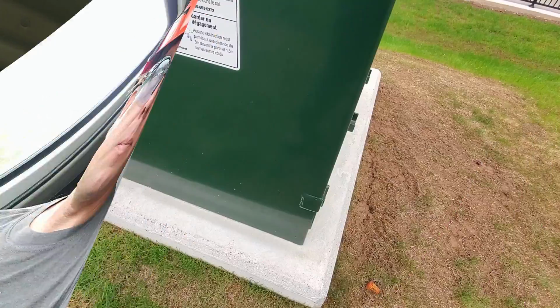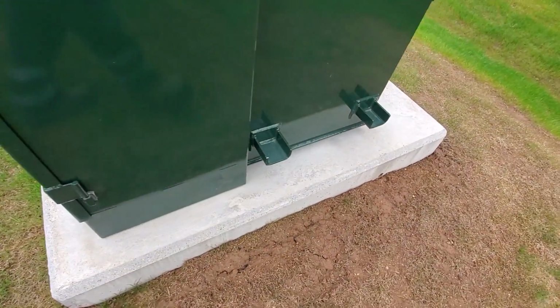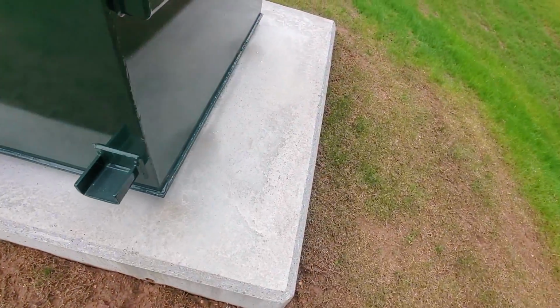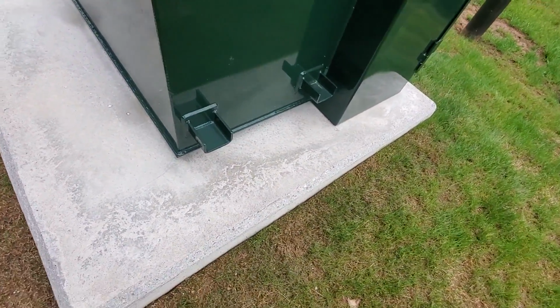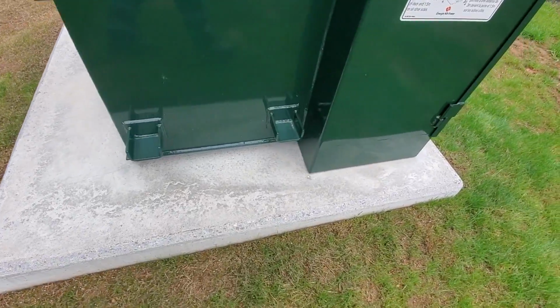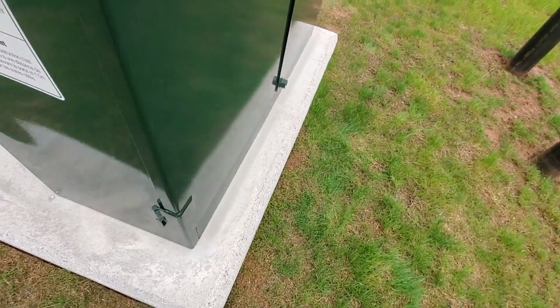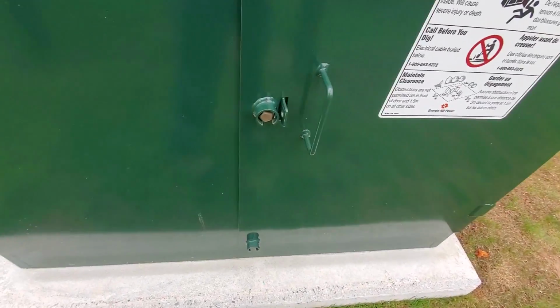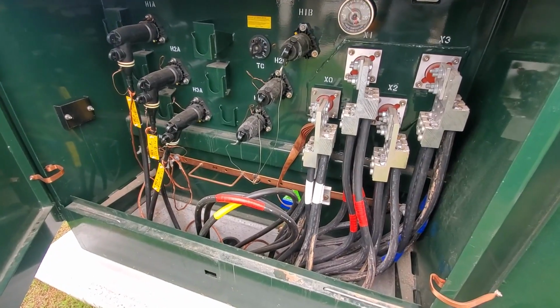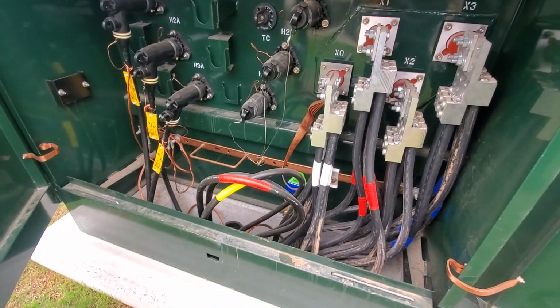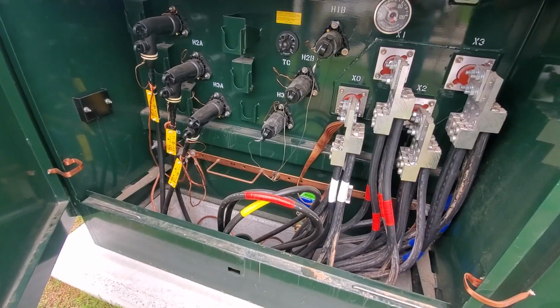First, checking the condition of the pad, keeping an eye out for any oil leaks, looking at the condition of the tank itself, the paint, looking for rust. Sometimes water can undermine the concrete pad. This one's brand new, so everything looks good. Checking inside, being careful for critters or hornets' nests as we open the door.